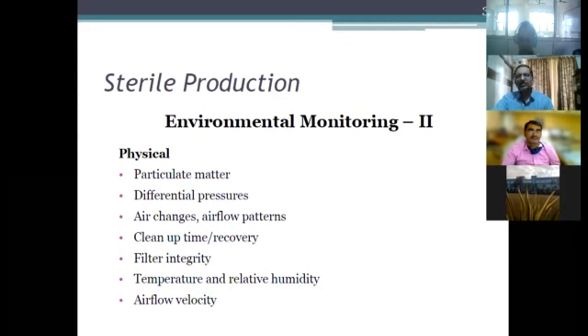It's very easy. You know the length of the room, breadth of the room, and height of the room. So you know the volume of the room in cubic feet. You want to change that volume 30 times. So multiplied by 30, you have the total volume of air which has to be handled in 1 hour. You select a blower that delivers that CFM, cubic feet per minute of air. Blowers are available in CFM capacity, or LPM, liters per minute. So do the calculation and select a blower with a higher capacity than what is required, and you can design it, and that will manage the air changes.